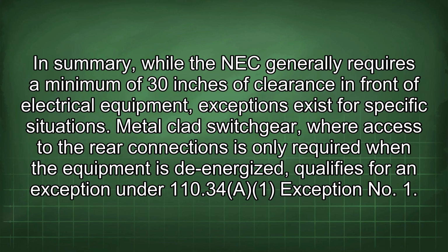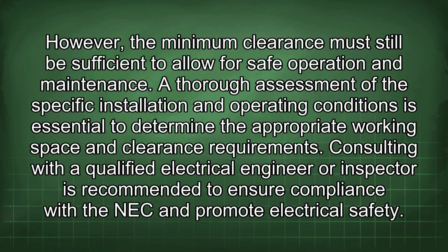In summary, while the NEC generally requires a minimum of 30 inches of clearance in front of electrical equipment, exceptions exist for specific situations. Metal-clad switchgear, where access to the rear connections is only required when the equipment is de-energized, qualifies for an exception under 110.34(A), Exception No. 1. However, the minimum clearance must still be sufficient to allow for safe operation and maintenance.